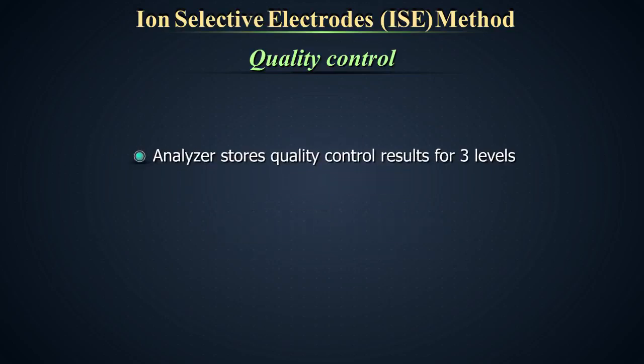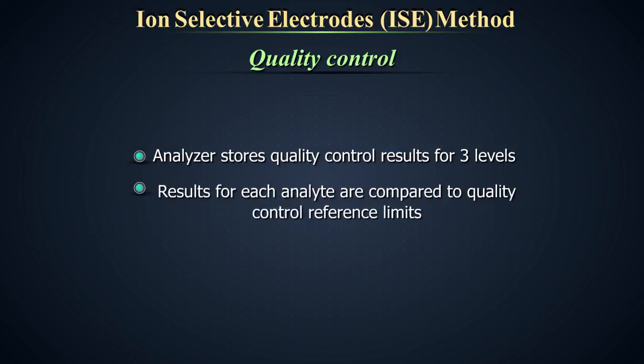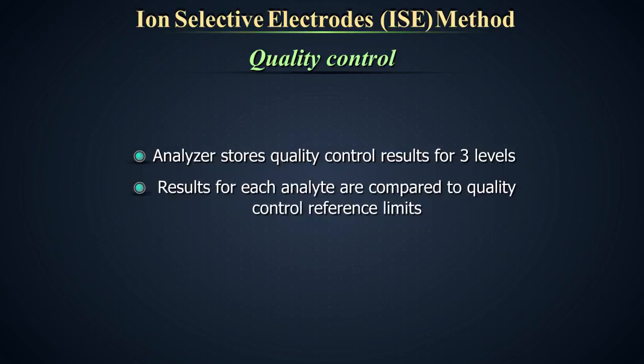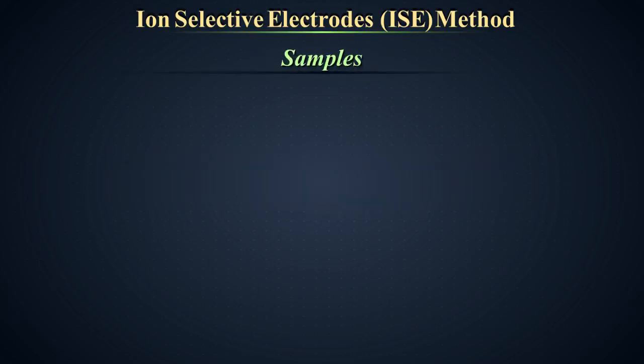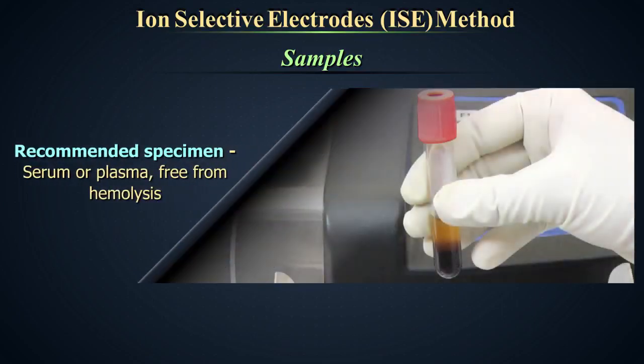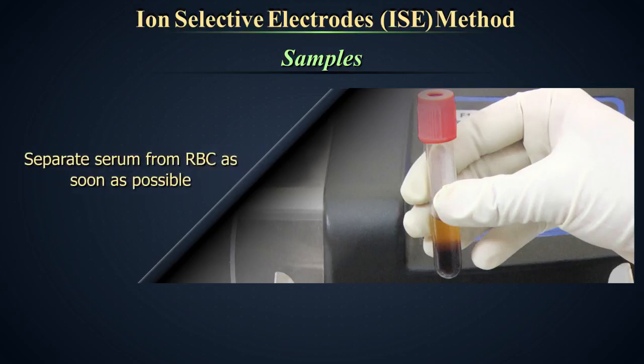This analyzer stores quality control results for 3 levels, a maximum of 31 for each level. The results for each analyte are compared to the quality control reference limits previously entered for the chosen level of quality control. Samples. All standard precautions need to be followed while handling samples. Serum or plasma, free from hemolysis, is a recommended specimen. Separate serum from red blood cells as soon as possible.